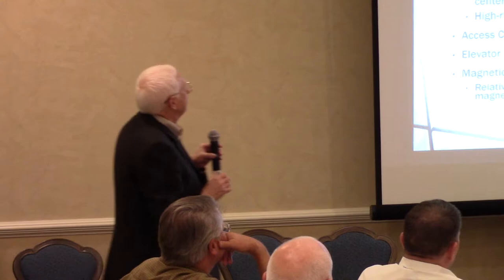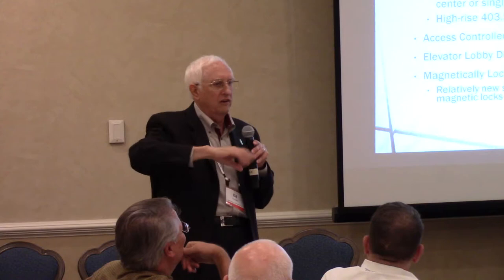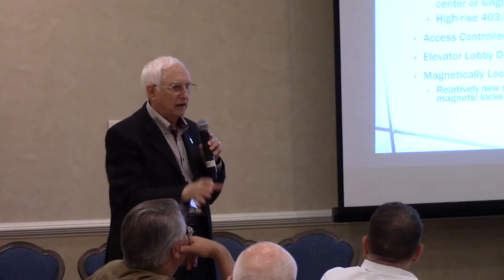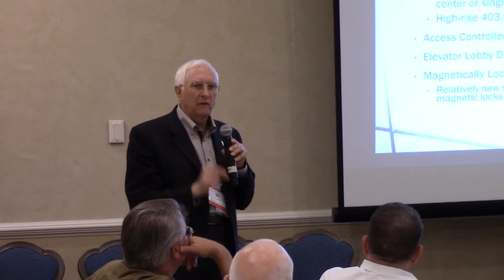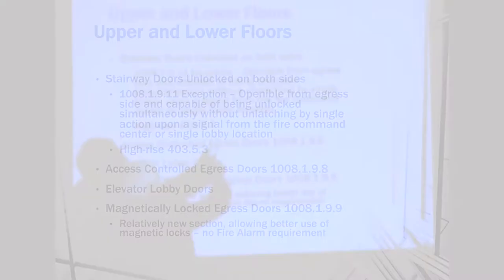You don't have to lock every stairwell door. You can leave floors three, four, and five unlocked in both directions if they open to a public hallway connecting stairways. But if a full-floor tenant wants to lock that door from the stairway side, then every one of those doors in the building — whether in the garage or floors above — has to unlock by that single action.